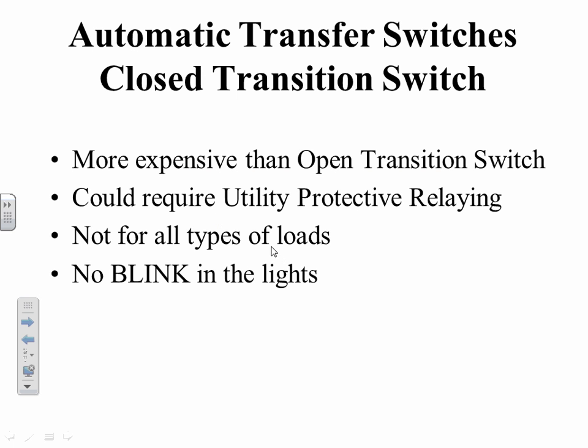Closed transition is not for all types of loads. UPS systems aren't a good one for this one because they might do some wild things. There's no blink in the lights. A good application for a closed transition switch is, if you think about it, warehouse lighting. It's a dumb load, but if it's the high discharge type that takes a long time to restrike, that's a good application for this type of a switch.